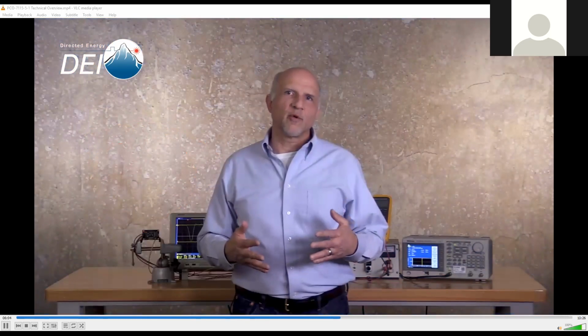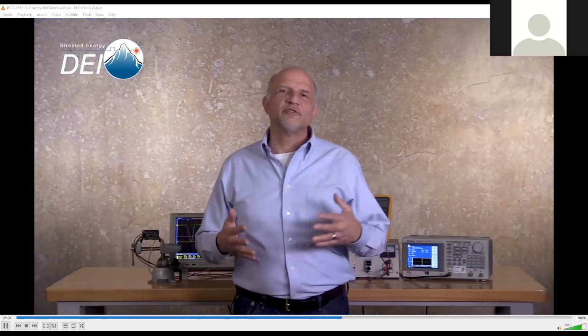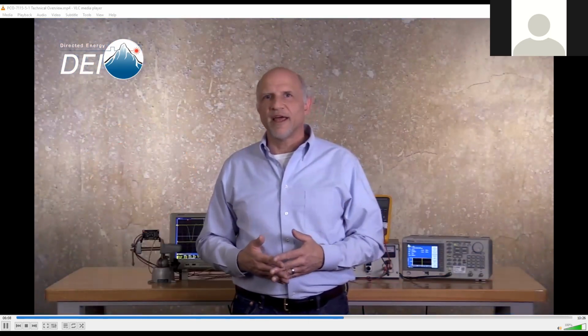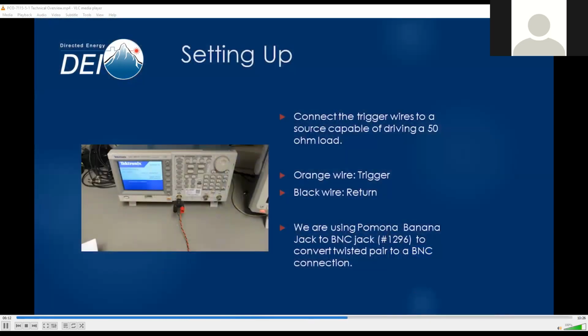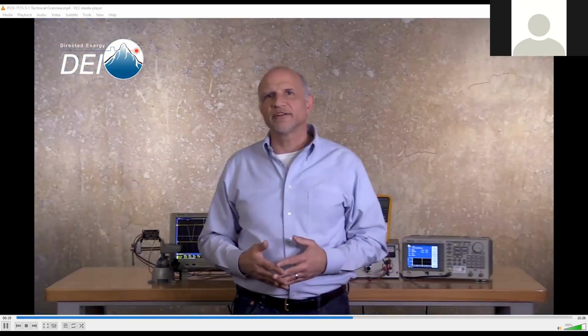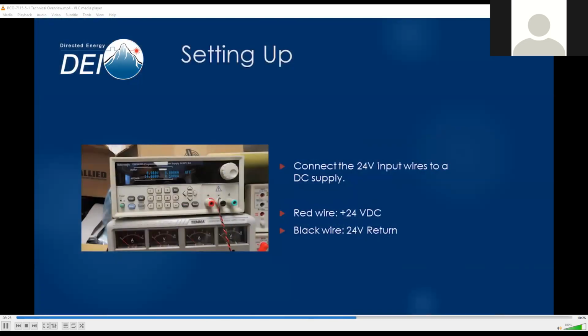To attach the trigger wires to the pulse generator, you'll use the orange wire as the trigger signal and the associated black wire as the return. For our demonstration, we used a banana to BNC jack to convert the twisted pair to a BNC connection. Now let's connect the 24-volt supply. The red wire is the positive 24 volts, and the black wire is the 24-volt return. In this case, our power supply has screw terminals, so no additional hardware was required.